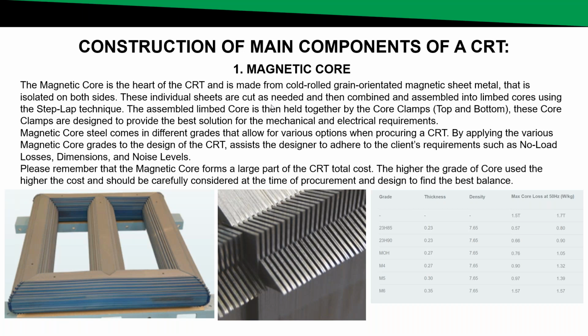Please keep in mind that the core of the transformer forms a large part of the total cost of the cast resin transformer. Taking this into account, the higher the grade of the core steel used, the higher the cost of the cast resin transformer will be. So it's always a good idea to find a good balance between performance and cost when it comes to your magnetic core.